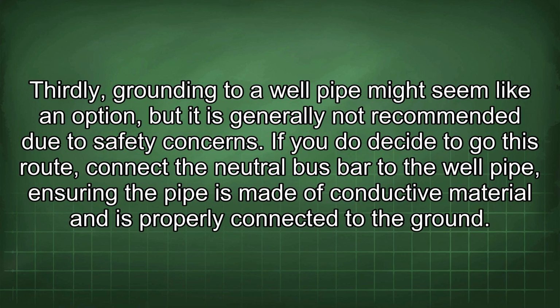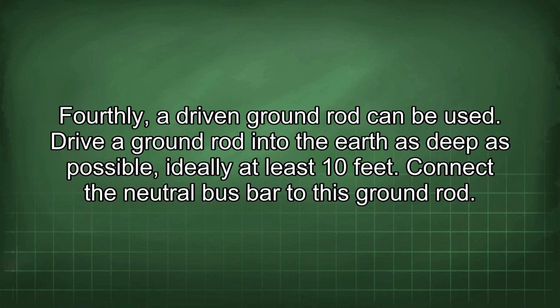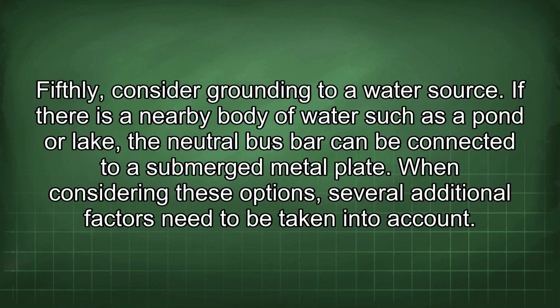Thirdly, grounding to a well pipe might seem like an option, but it is generally not recommended due to safety concerns. If you do decide to go this route, connect the neutral bus bar to the well pipe, ensuring the pipe is made of conductive material and is properly connected to the ground. Fourthly, a driven ground rod can be used. Drive a ground rod into the earth as deep as possible, ideally at least 10 feet. Connect the neutral bus bar to this ground rod. Fifthly, consider grounding to a water source. If there is a nearby body of water such as a pond or lake, the neutral bus bar can be connected to a submerged metal plate.